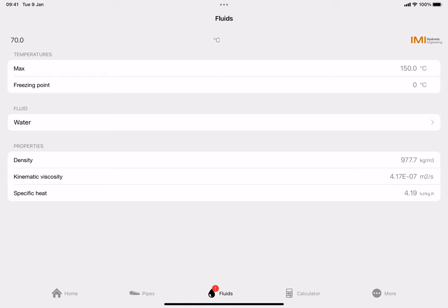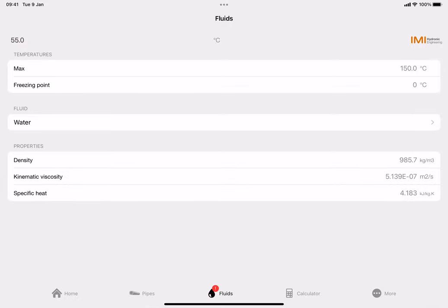Most other training facilities we work alongside - the Heating Academy in Northampton and Heat Geek - will round those figures up to 4.2, which is perfectly fine if you're just doing standard domestic calculations. This calculator will change that by default as soon as you change the flow temperature. So we're designing at 55 degree flow temperature, we'll keep it at 4.183, and at this point your calculator is completely set up.